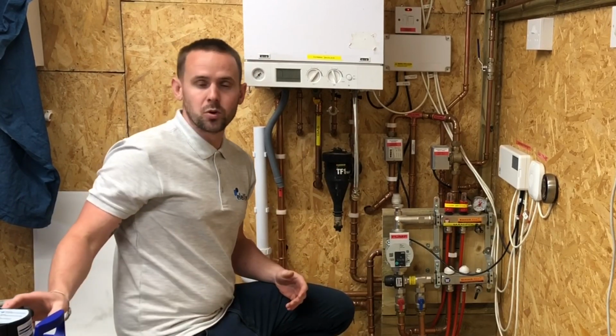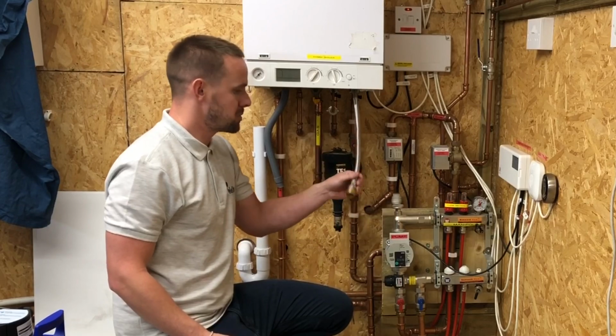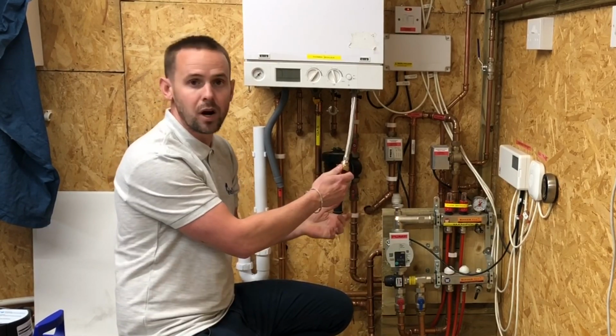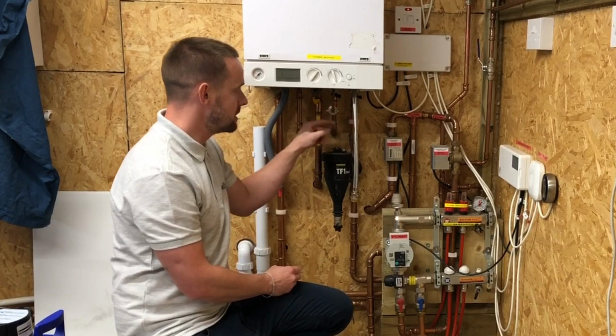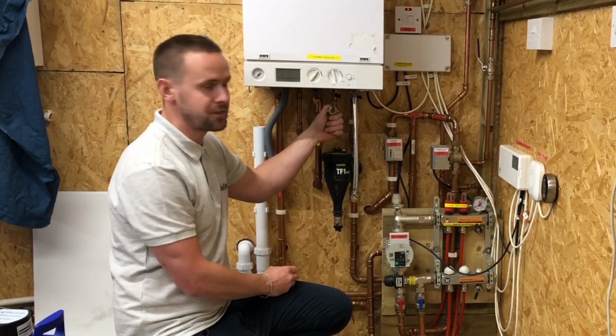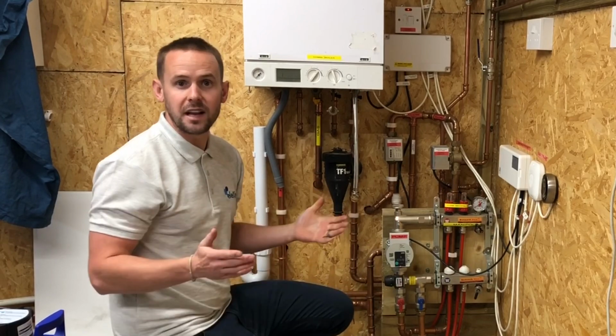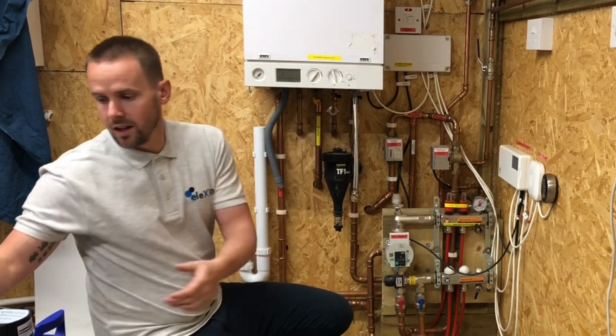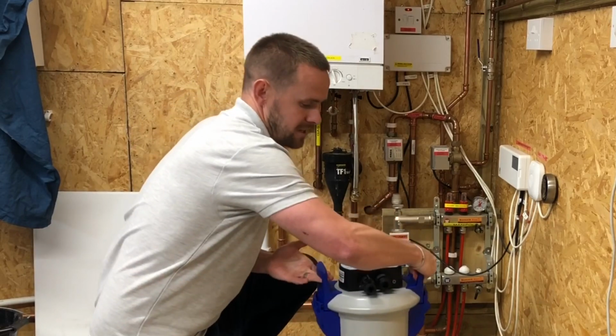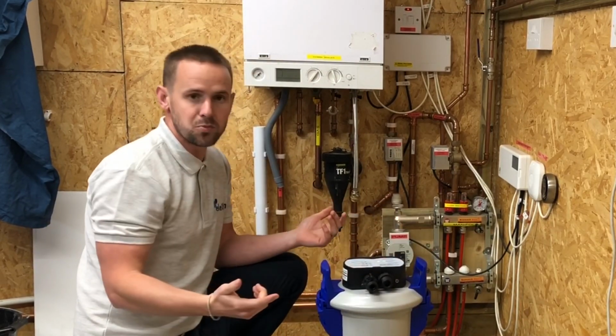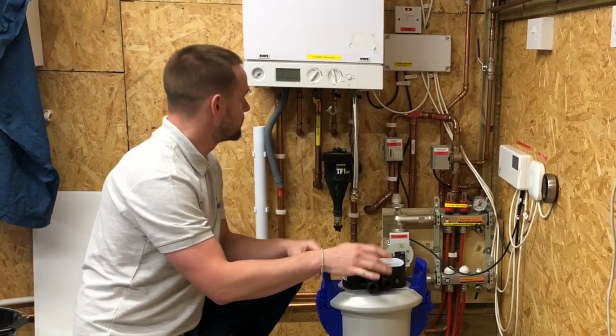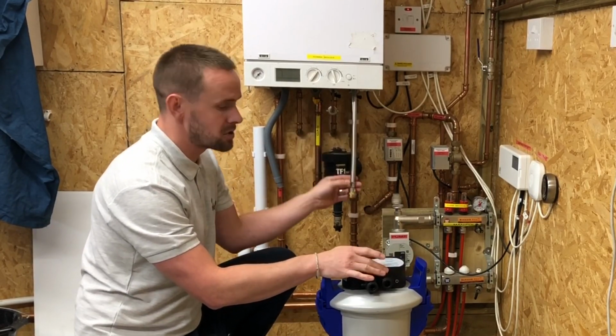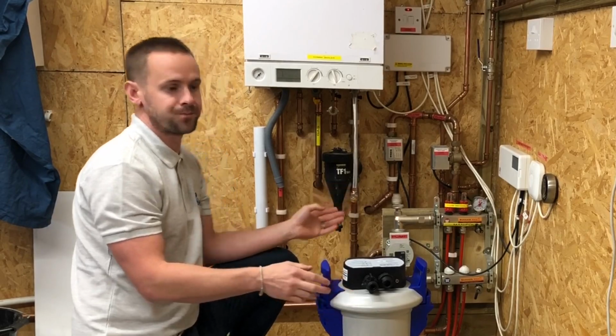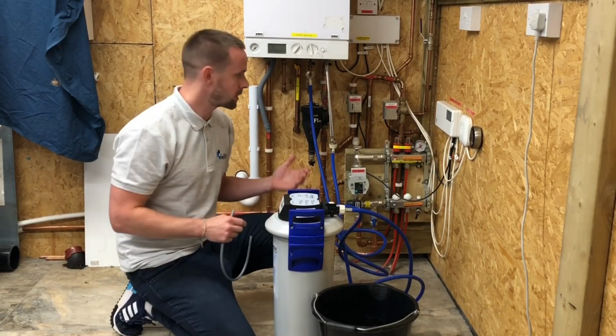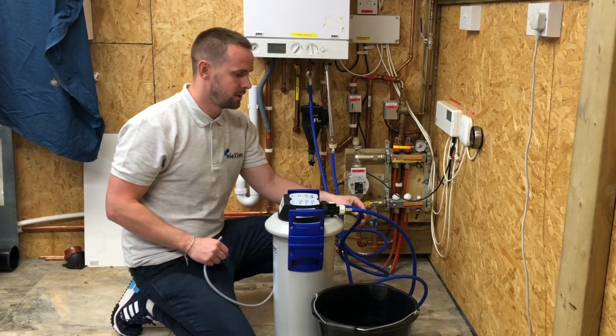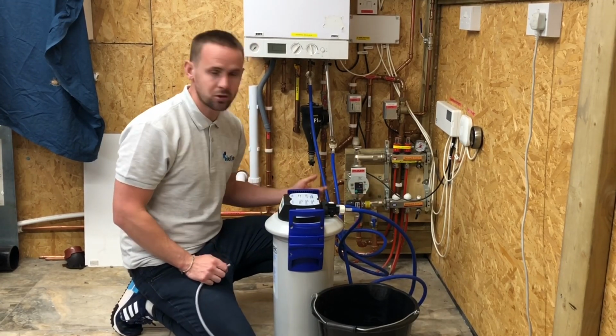The Clarimax has got 3/4 connections. These are obviously 1/2 inch. So we've got some little adapters here on little filling loop hose, and then we just utilise the little bend that comes with the boiler, and again put a little adapter on it, so we're ready to fill. So we're ready now to connect our hoses to the system. The Clarimax itself very simply tells you in and out. It's pretty simple. So you connect your inlet to the mains water, and then on this one it's the return, which will go to the outlet. Right, we've got our hoses connected now. We've simply utilised some fairly inexpensive washing machine hoses. They seem to work quite well.